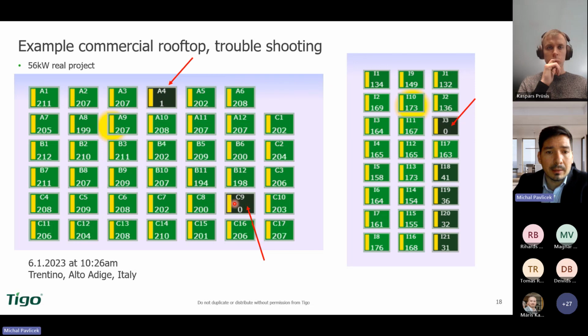If you look at a simple comparison between the power, you see immediately you have an issue. Of course, there might be some extreme shade. So you can also say, okay, maybe this is not happening, maybe if I go to 11 it will disappear, but unfortunately not. If you repair those modules, then of course you immediately get probably 30% more power in those strings.